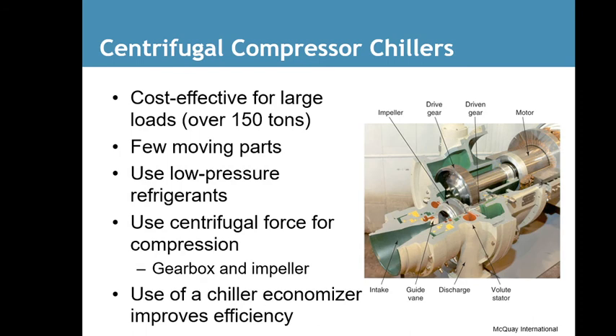Centrifugal compressor chillers are cost effective for large loads over 150 tons. Few moving parts, uses low pressure refrigerant, uses centrifugal force for compression, gearbox and impellers. The use of chiller economizers improves efficiency.